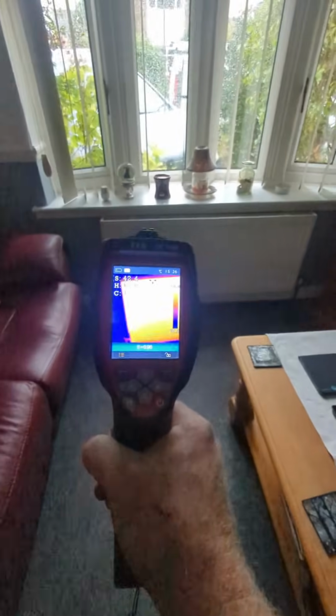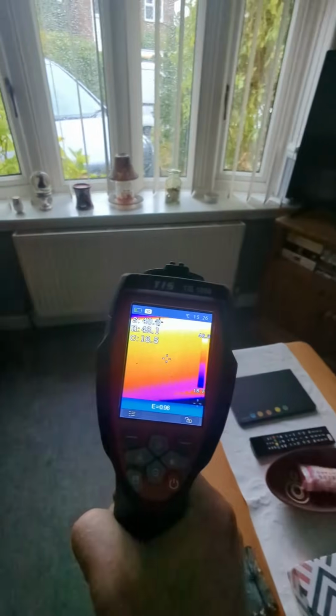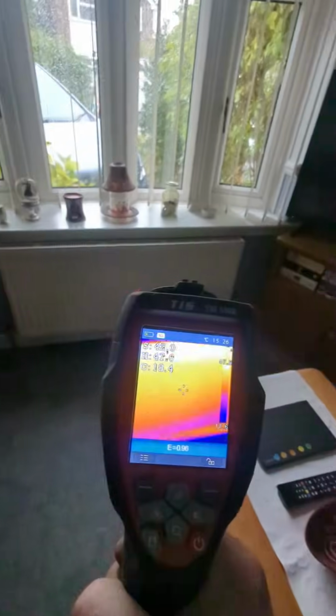One radiator wasn't heating up, so I'm just using the thermal camera to check that my repair has worked. The last part of the job would be doing all our safety checks, checking the combustion, seeing if the gas valve needs adjusting, checking our pressures and our carbon dioxide, carbon monoxide, etc. We'll fill out the service sheet detailing all the work, and we're ready for next year.